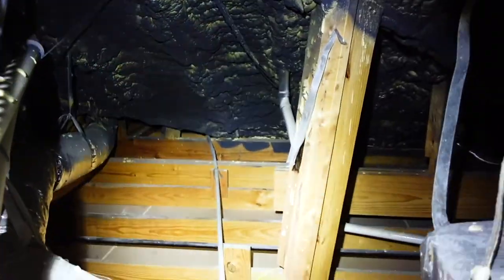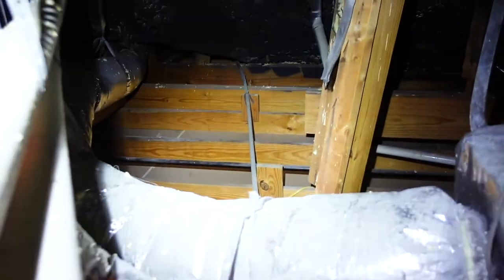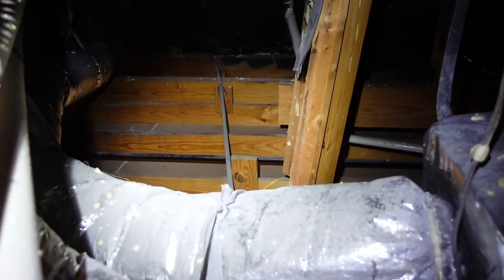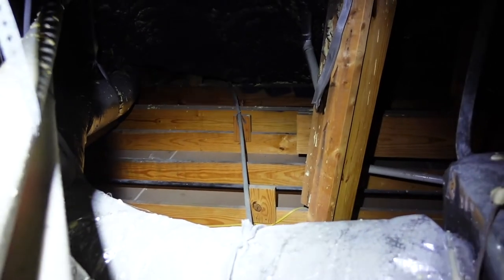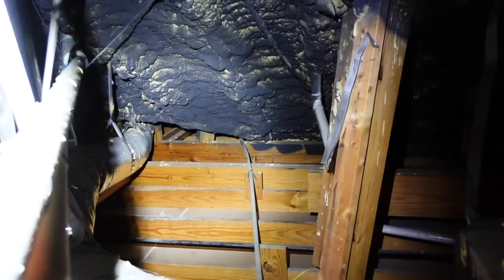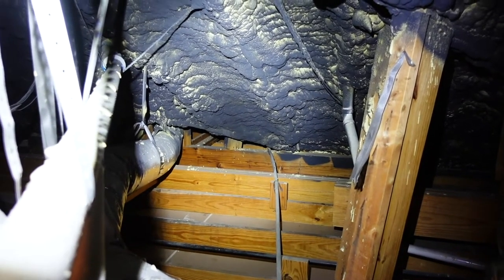In the attic we always look around as much as possible. Peering around this purlin support, I found the primary drain pan drain line has fallen off the blocking at the bottom, so it goes up to the second blocking and is not properly sloped. We'll ask that they re-slope it, get it back on the blocking, and secure it in place. That comment is part of our comment package, which you can purchase on the HIW website.